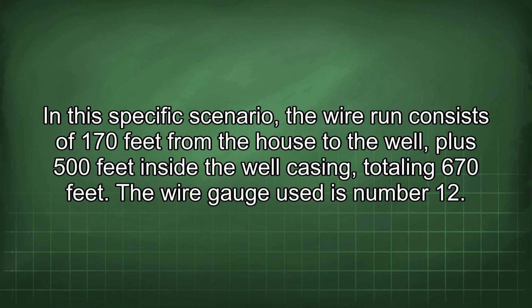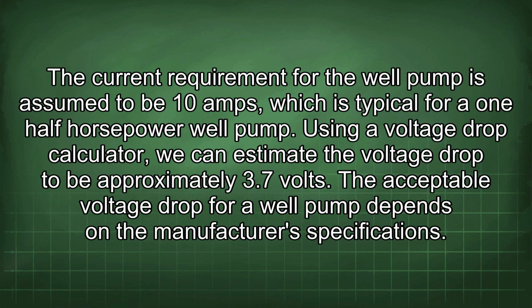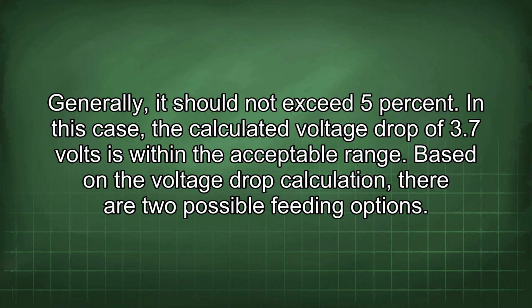The wire gauge used is number 12. The current requirement for the well pump is assumed to be 10 amps, which is typical for a 1/2 horsepower well pump. Using a voltage drop calculator, we can estimate the voltage drop to be approximately 3.7 volts. The acceptable voltage drop for a well pump depends on the manufacturer's specifications. Generally, it should not exceed 5%. In this case, the calculated voltage drop of 3.7 volts is within the acceptable range.